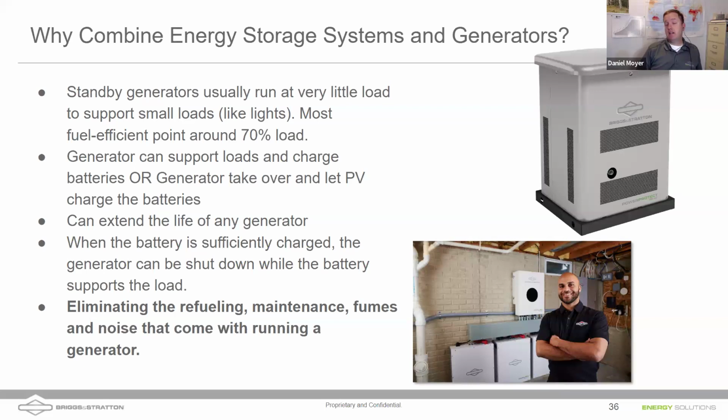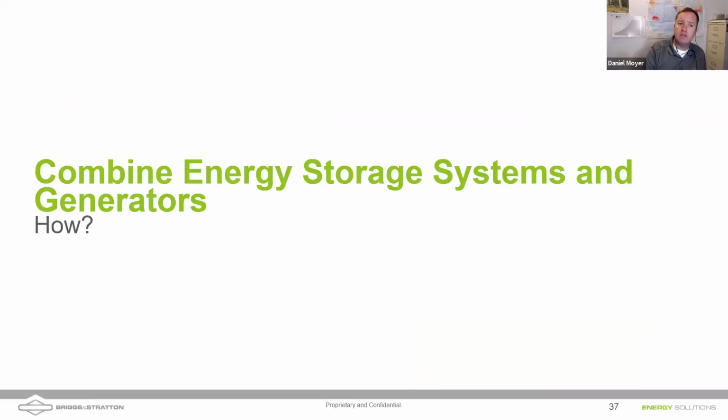Yeah. And I think I have a slide coming up here too, which is the opposite, right? If you have a 26K generator and maybe we're using a SolarArc 8K, well, the SolarArc 8K isn't going to be able to take in 26K from a generator. So what you've done is oversized the generator. It'd be more appropriate to size this 13K generator that you see on the screen. An 8K is only going to be able to pull in a given amount. So great points, Nathan. Thank you so much.